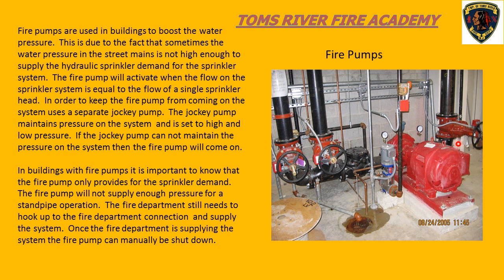Alright, this is what powers the fire pump, and it's a big electric motor. Over here we have zone valves that go up to different areas of the building to supply water to the sprinkler system. If you are dealing with a fire pump, once you get the fire department connection hooked up and get water into the building and start pumping, it is okay to send somebody in, if it's safe, to shut the fire pump off. We don't want the fire pump running once you're hooked up to the fire department connection and pumping.